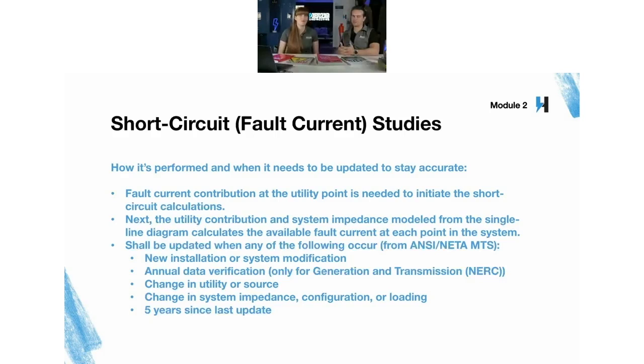Sure. So in the NFPA 70B, of course, it's the brand new standard on the block. And Chapter 6, short circuit studies, is now required to be updated not to exceed 5 years. But if you look one line above that, it says shall be updated when changes occur in the electrical distribution system that could affect the results of the study. So 5 years really is the minimum rule. That's if you live in a fairyland and haven't had any changes in your distribution system, worst case, all you're doing is getting updated utility fault current values.